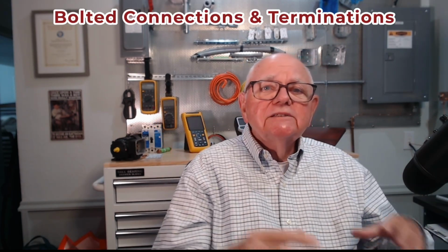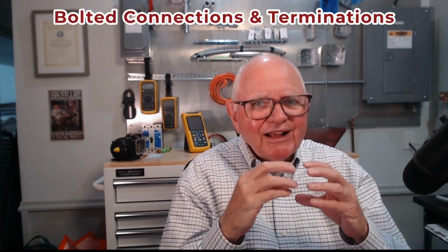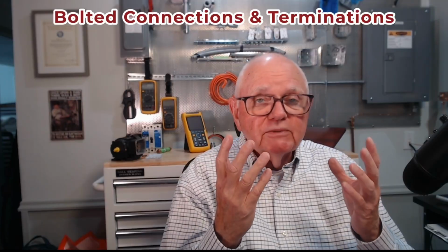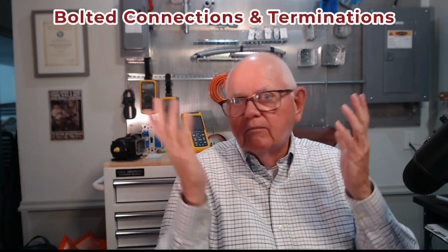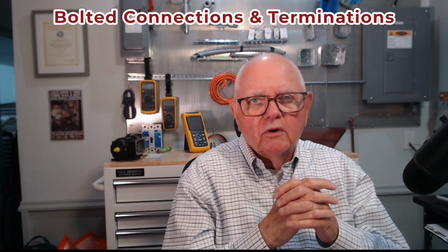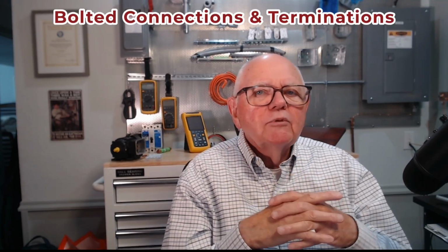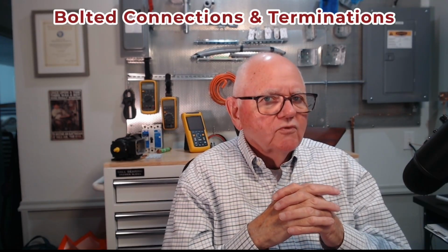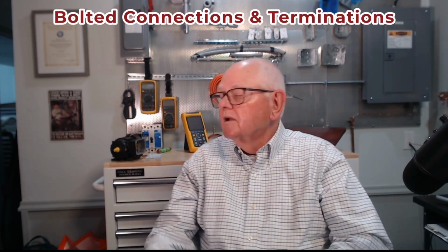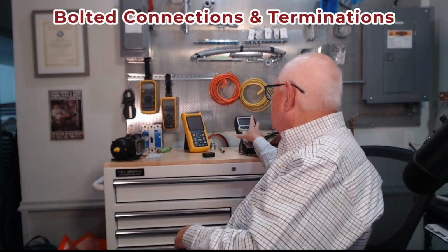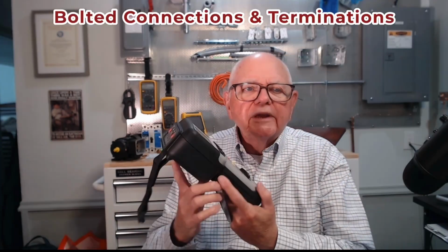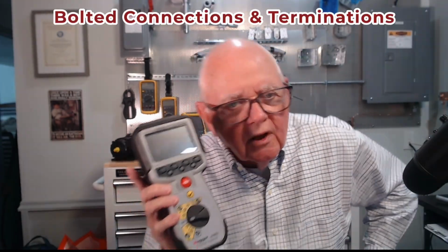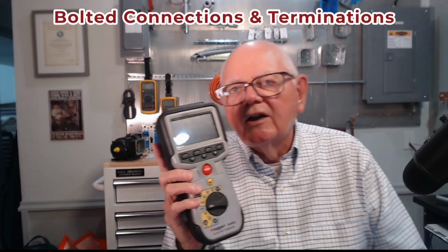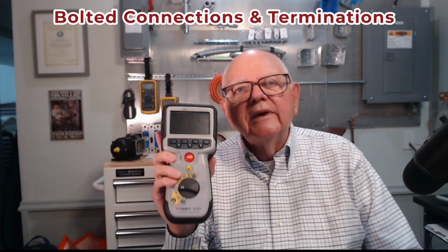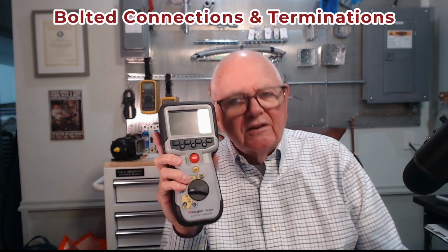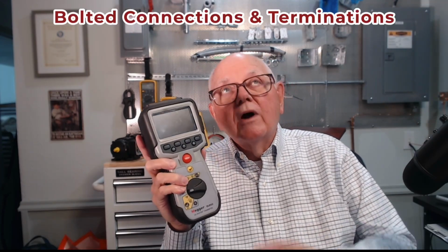In reality, when I test those bolted connections, the resistance values are much, much lower. So if I were to take a multimeter and put on there, I would get 0, wouldn't I? But in reality, it's probably in the millionths of an ohm range. So I'm going to use a different meter for that. I'm going to use a micro-ohmmeter, what's sometimes called a digital low resistance ohm meter, or DLRO. On this micro-ohmmeter, it will read out down to millionths of an ohm. So that's what?